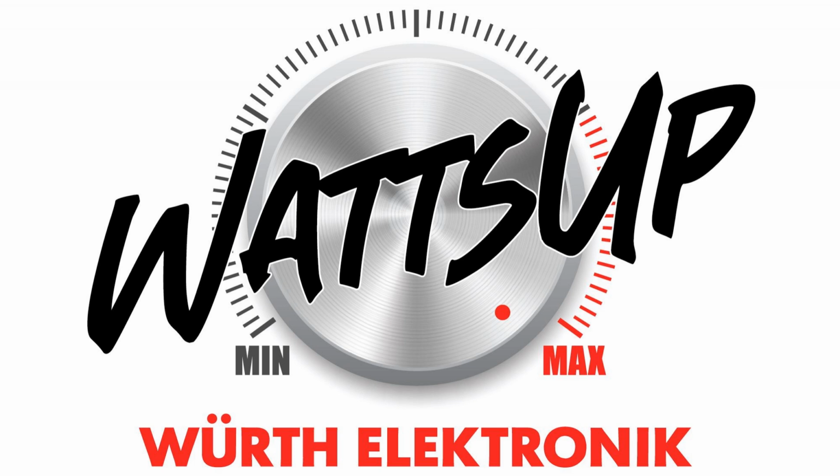Then before releasing a product, we have to make a so-called stress test for the rated voltage. That means we put several equal components side by side, or actually in parallel, on a PCB. And then before we apply the rated voltage for 1 hour, we have to measure the main parameters like main inductance, DC resistance, and insulation voltage.